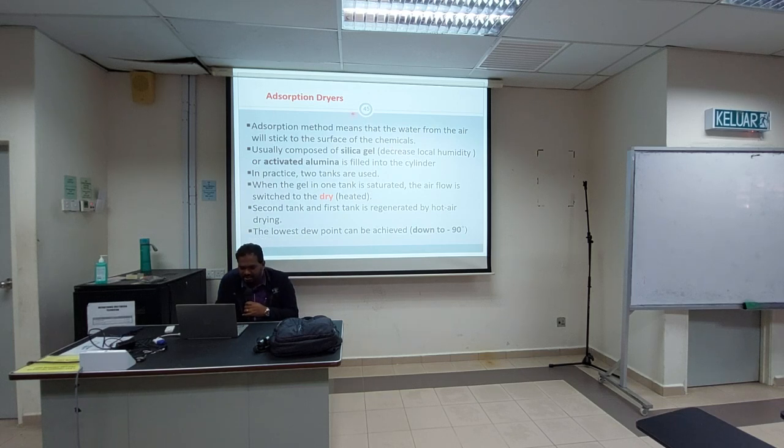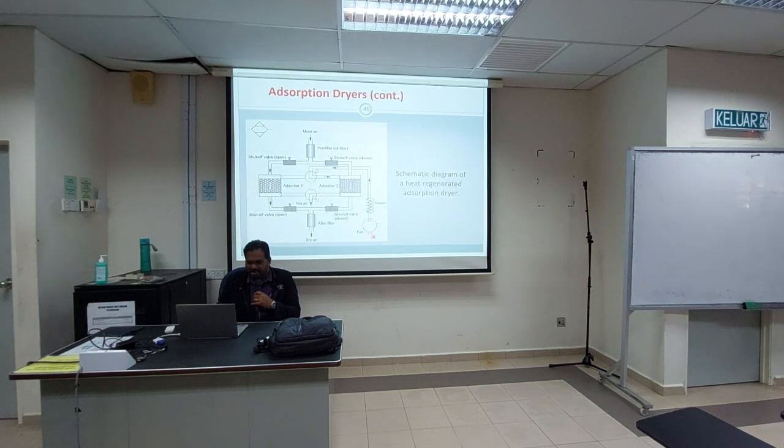So that's the difference between adsorb and also absorb. So in practice you are using 2 tanks. So when one is saturated, the flow will switch. The lowest dew point that can be achieved is -90. Okay, so boleh tengok dekat sini. So ini adalah adsorption dryer.